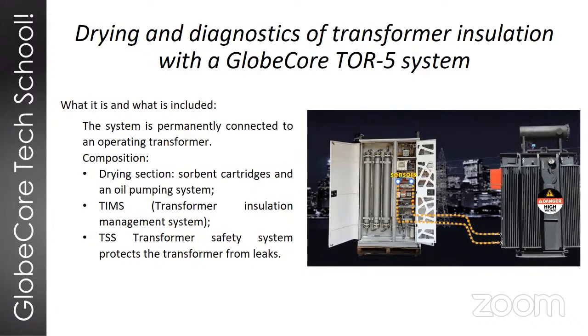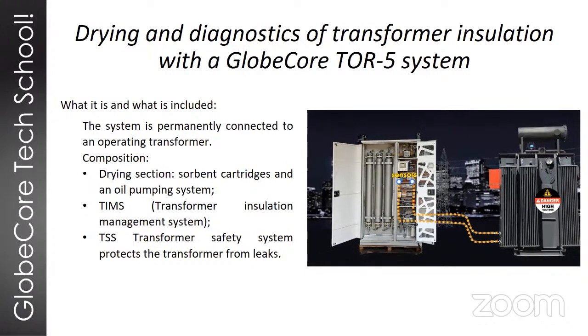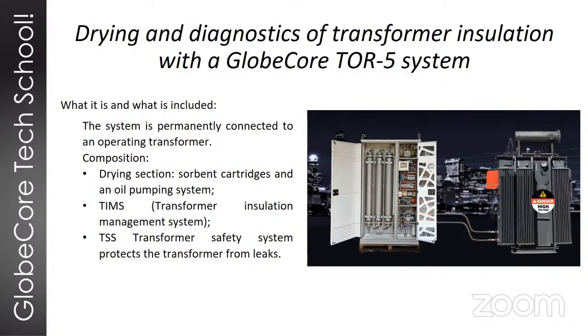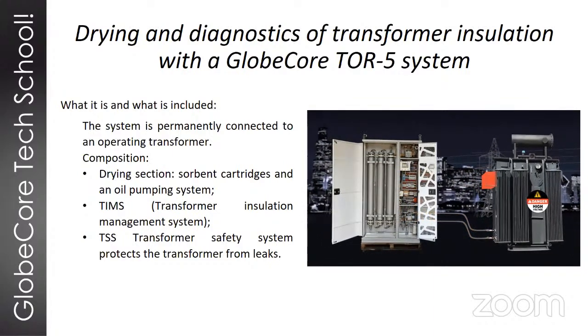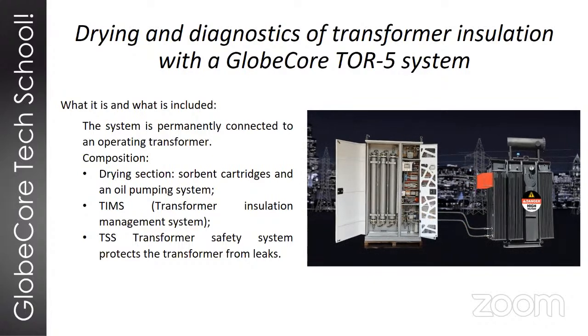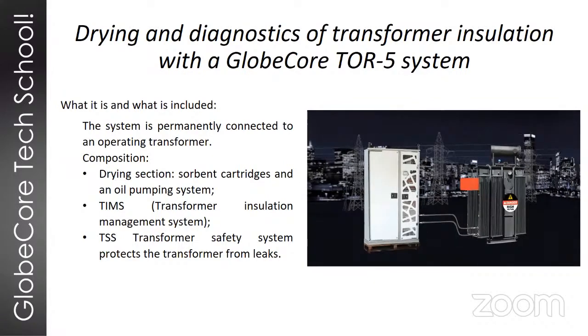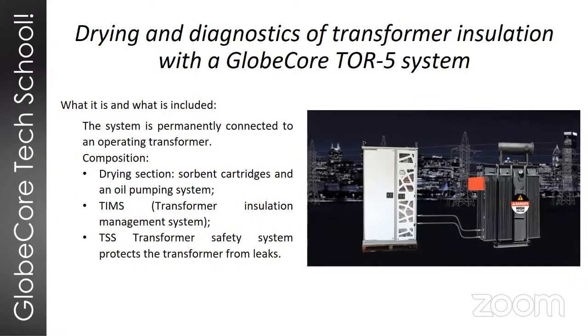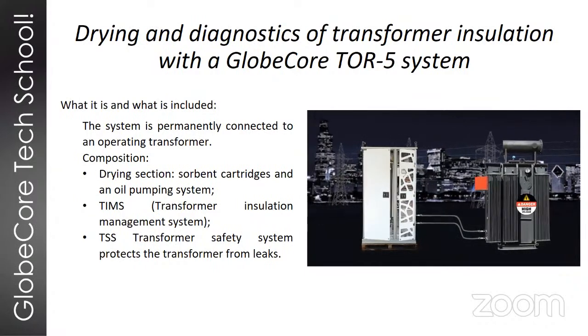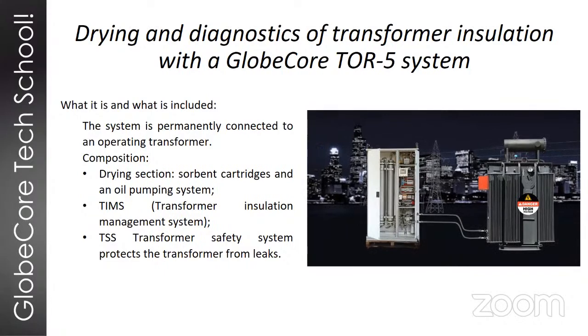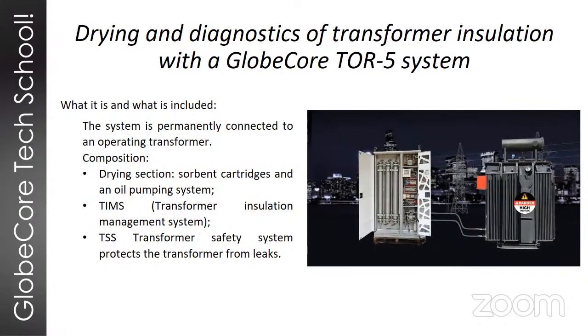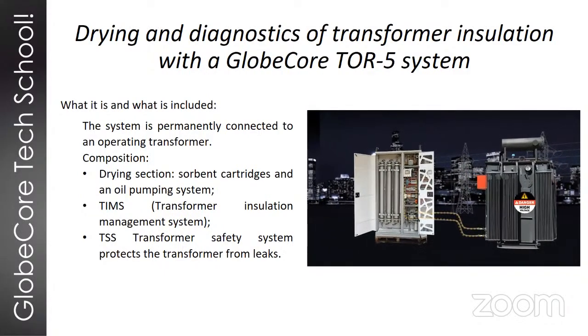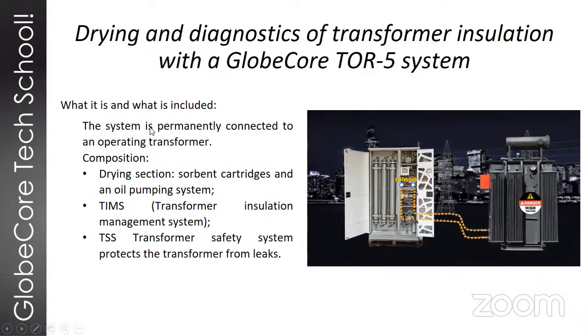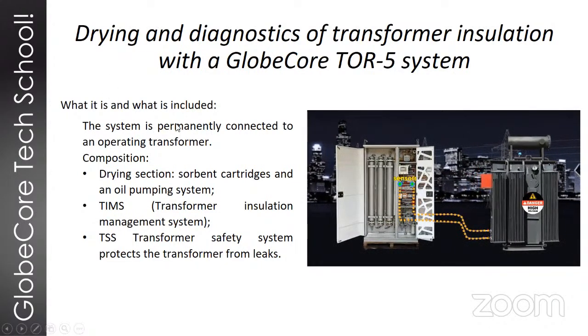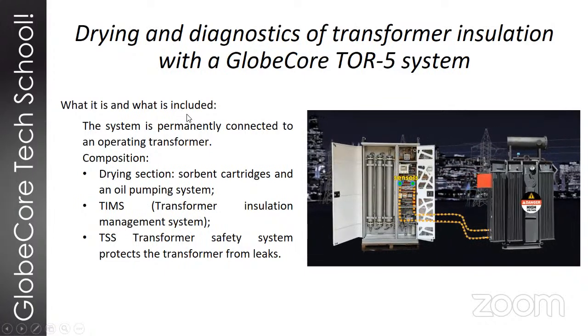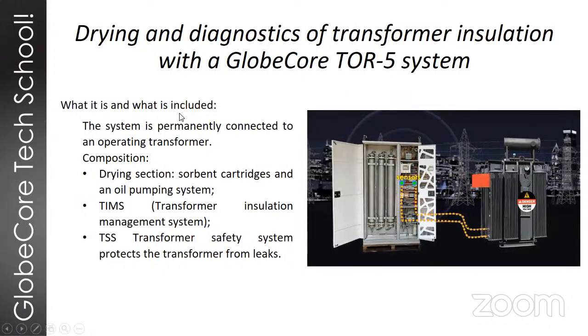One big advantage of the TOR5 is its simplicity. Basically, it consists of 3 sections enclosed in one case. There is the oil processing section for removal of moisture from the transformer oil. It has 3 adsorbent cartridges and a pumping system for the oil. So when the parameters of the oil reach certain limits that are preset by the operator, the TOR5 automatically switches from the diagnostics or monitoring mode into the filtration and drying mode for the oil.